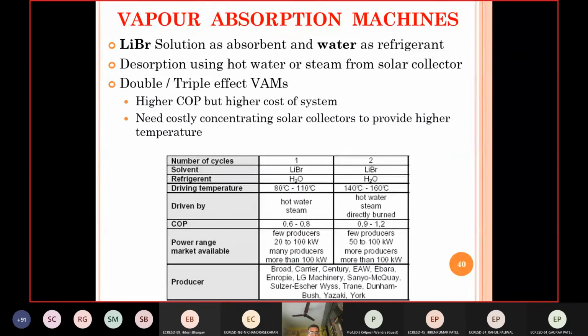So absorption machines, as you can see here, single effect and double effect is compared. The driving temperature for single effect could be 80 to 110, while for double effect it would be 140 to 160. So here you can use hot water or steam. Here you have to use pressurized steam. Okay. Here higher temperatures are required, so the solar collector initial cost will be higher.